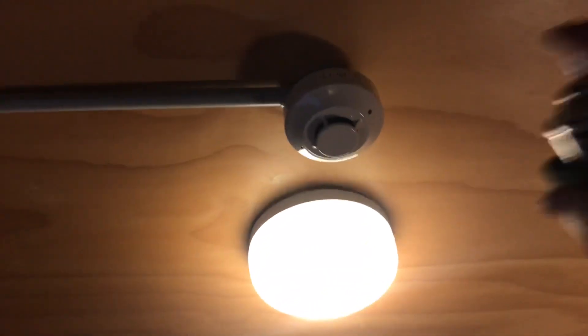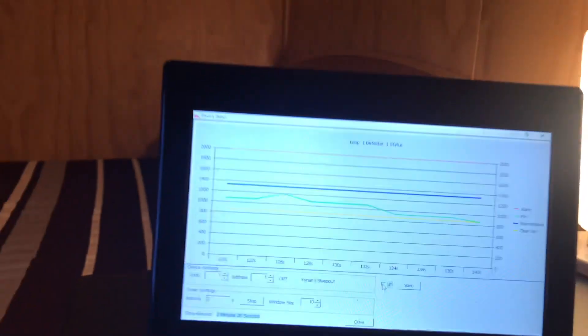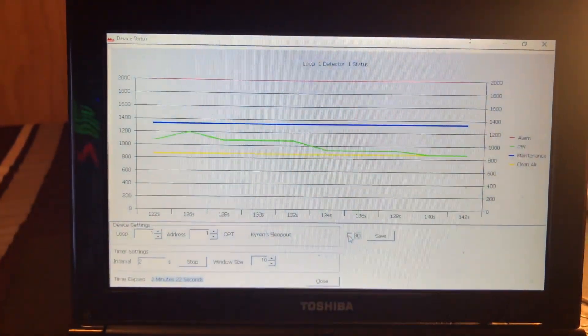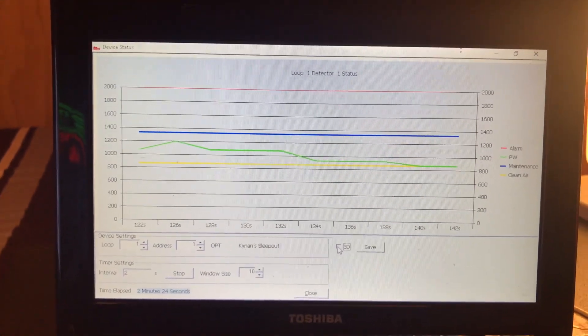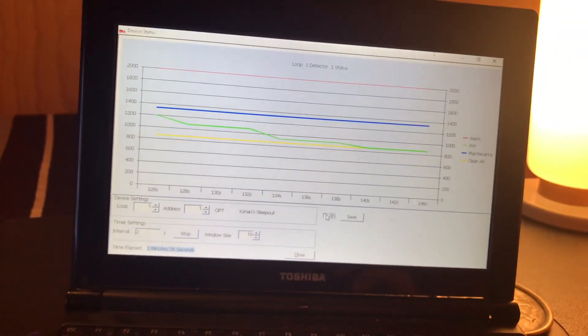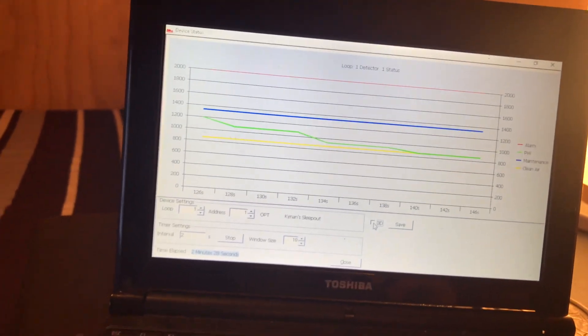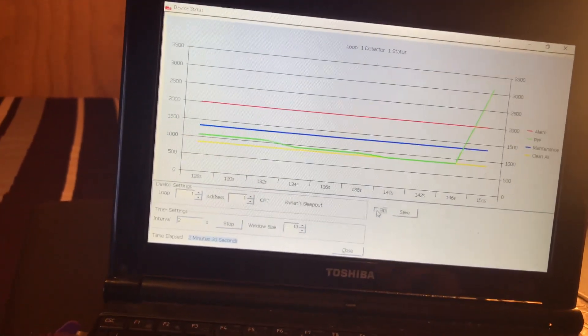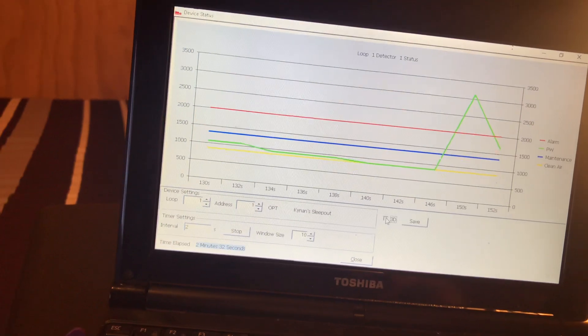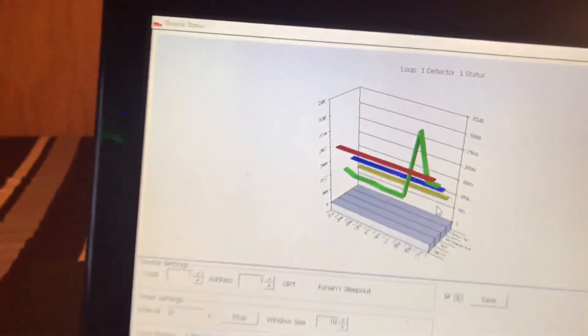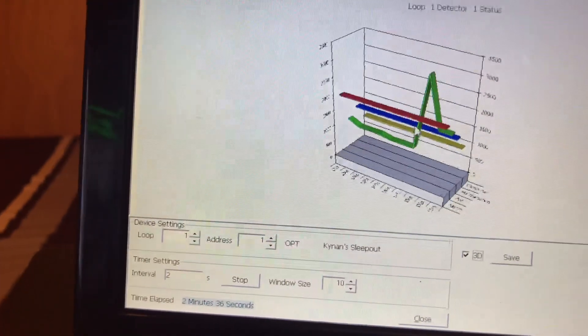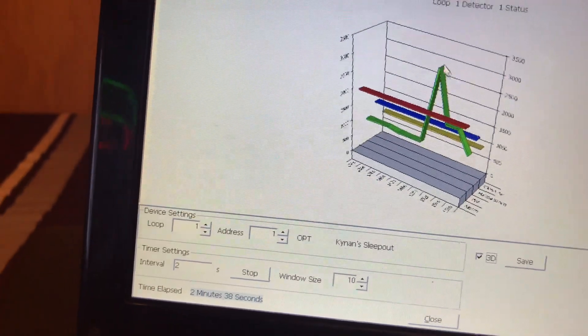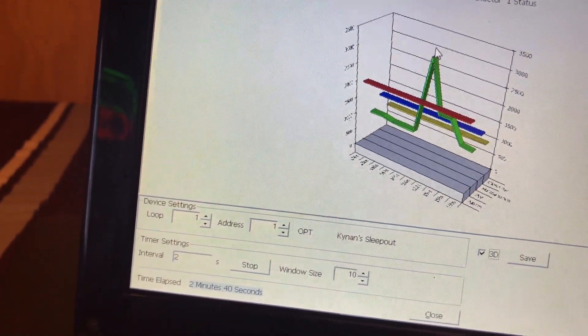Let's give it a little bit more now. And you should see the value really sustain its high level. That should be more than enough to set it off. Now it should rise again. So again, we're looking for that green bar. The panel's actually just gone into fire. You can see on the 3D view, that was just before when I sprayed the smoke, the value shot up way up to 3000.